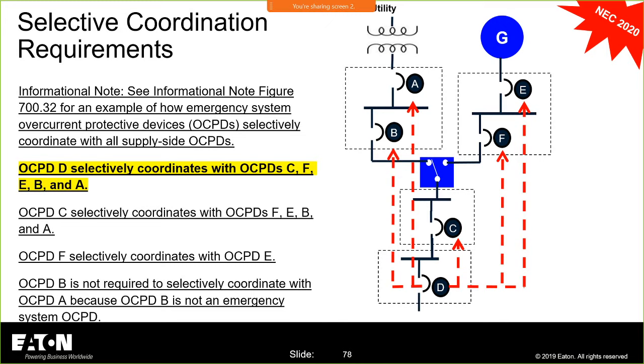I'm going to go to Article 700, and 700 says selective coordination. It says emergency system overcurrent devices shall be selectively coordinated with all supply side overcurrent protective devices. So emergency system overcurrent devices. Device D is an emergency system overcurrent device. It has to selectively coordinate with all line side. The fact that A and B are on the normal side, the onus of selective coordination is on D.